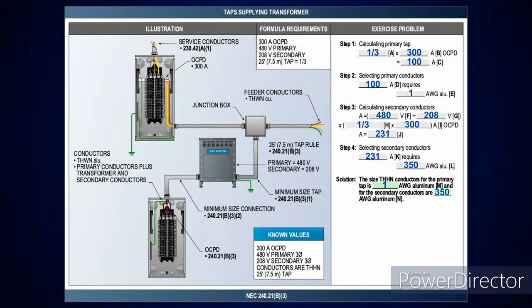This is where we actually have a transformer in the tap. And I said on the secondary, you got to get the ratio of the transformer. And in this case, we have a 480 volt primary and a 208 volt secondary. The upstream overcurrent protection device is a 300 amp. So when I'm doing the primary tap, I'll take the 300 amps at a third. That's going to give me 100 amps. Go to table 310.16. The next size above that or equal to that is 100 amps, which is a number 1 aluminum conductor. And this is a trick question here, because what will happen if you're taking the test, you'll look at the conductors we gave in this case, and we're telling you we're using THW and aluminum instead of copper here. So you got your first column, then you go over the next set, you'll see the 60, 75, 90 C over there, and that'll be your aluminum conductors.